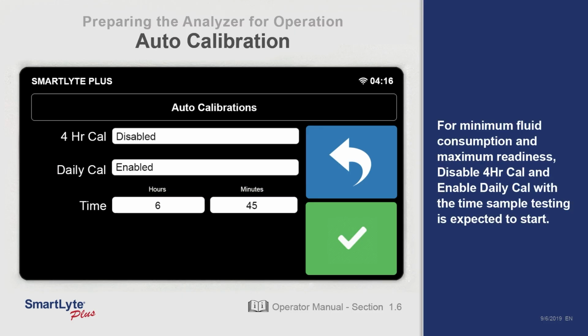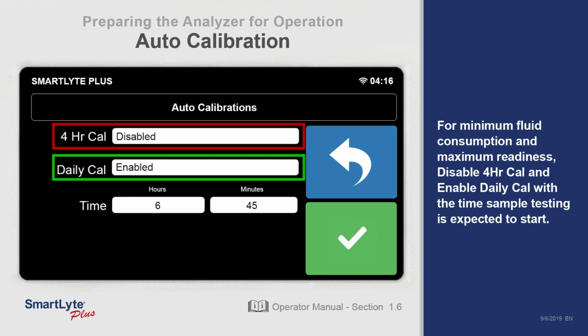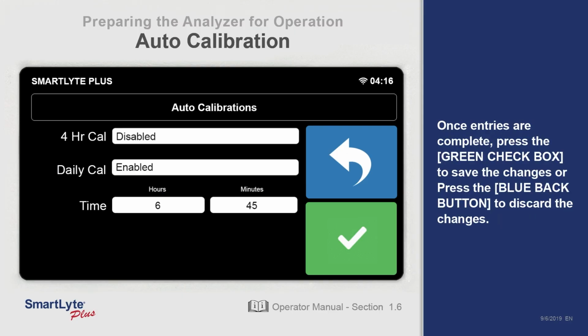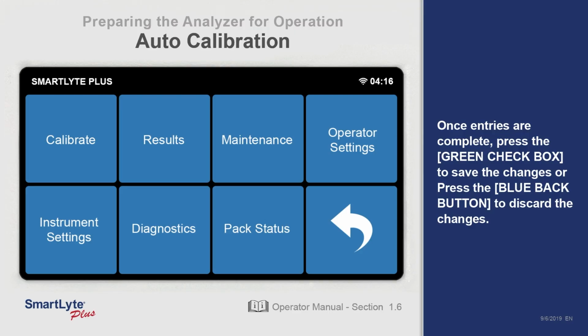For minimum fluid consumption and maximum readiness, disable 4-hour calibration and enable daily calibration with the time sample testing is expected to start. Once entries are complete, press the green checkbox to save the changes or press the blue Back button to discard the changes.